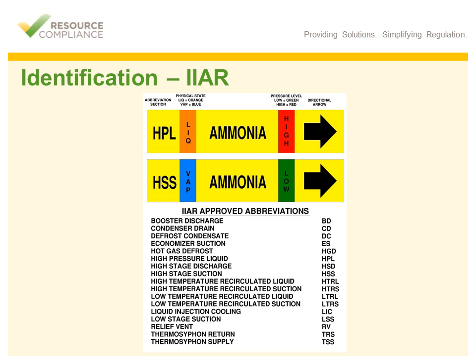The International Institute of Ammonia Refrigeration, or IIAR, has also developed a labeling system for ammonia pipes that has been widely adopted in the ammonia refrigeration industry. The IIAR system recommends that each pipe is labeled with a yellow label containing the following five things: one, the word ammonia in black font; two, a directional flow arrow; three, a pressure band indicating whether the pipe is under high or low pressure; four, a physical state band indicating whether the pipe contains liquid or vapor; and five, a service abbreviation which indicates the function or service of the pipe. A list of a few of the recommended service abbreviations has been included on this slide.